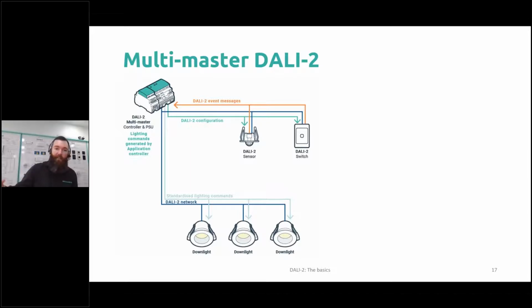And what information it sends is configurable via the DALI standard. So actually giving these things an address, telling this device what information you're interested in, that's all part of the standard. But what it doesn't do is talk to any lights. It's not going and saying, hey, light 4, turn on. All of that is then run by your application controller.